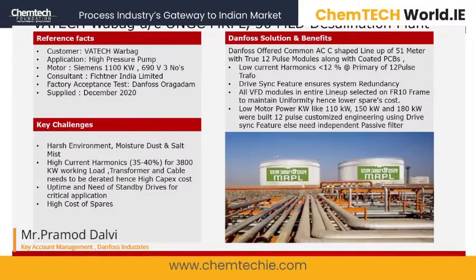So what Danfoss has done is we have offered a common AC lineup, a C-shaped lineup with a true 12 pulse module and definitely coated PCBs, which we offer as default in this segment. So low harmonics: compared to AFE, which gives 5%, this solution gives below 12%. But still you are meeting IEEE at the primary of the transformer. Then the drive sync feature, which I will explain in the next slide, ensures system redundancy, and if your application is critical, this is very, very helpful.